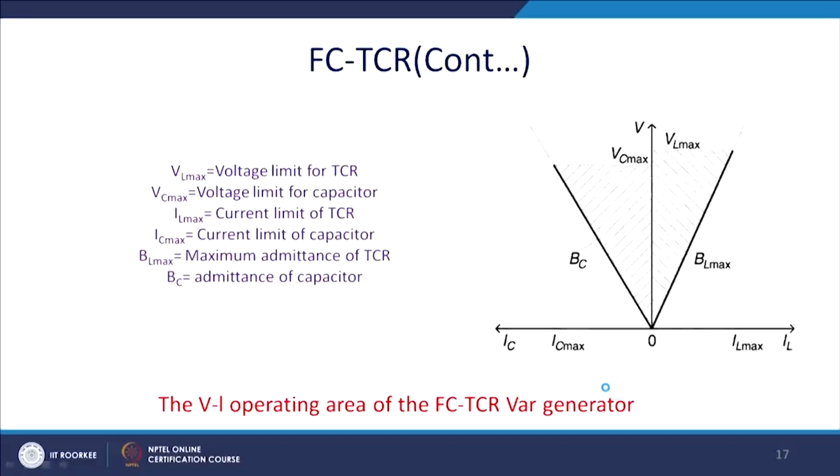Now, this is the graph, the fixed graph for this admittance. So, there is a shunt compensation. Ultimately this is the Imax and this is the BL max. Please note that voltage swells up for the capacitive compensation, so for this reason you cannot use the total rating, but generally voltage sags for inductive compensation. So, the terminal voltage can be higher than the rated voltage.